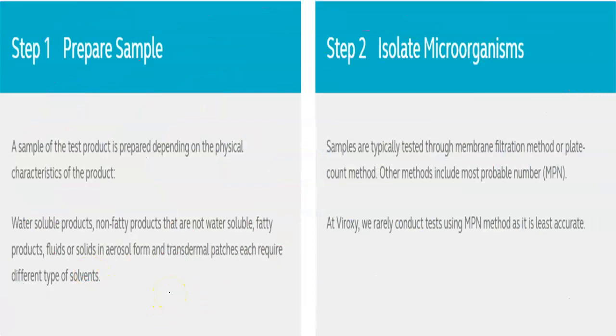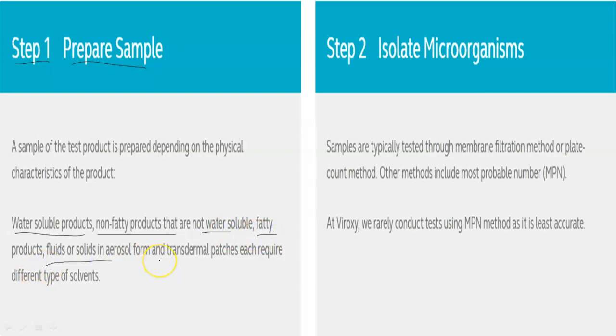This is the procedure of how the BioBurden test is performed, explained in brief — in the next video we will see detail about the aim, procedure, requirements, and results. The first step for the BioBurden test is preparation of the sample. The sample of the test product is prepared according to the physical characteristics of the product. Generally, water-soluble products, non-fatty products, fatty products, fluids or solids in aerosol, or transdermal patches each require different types of solvents.